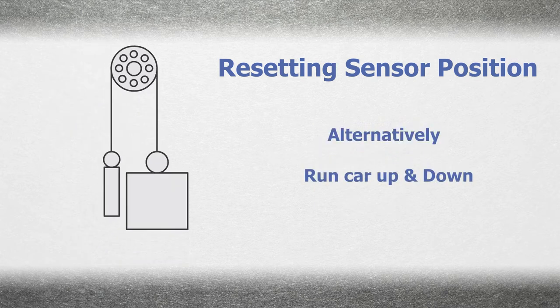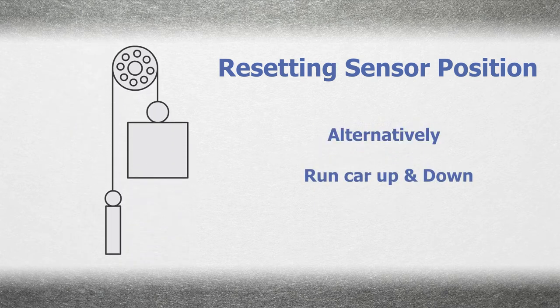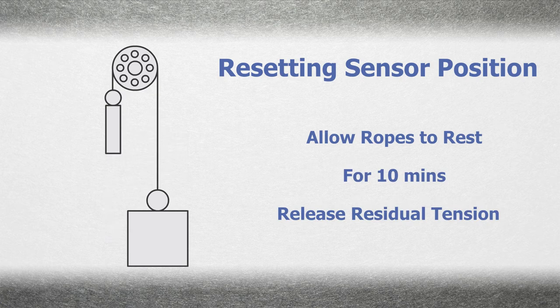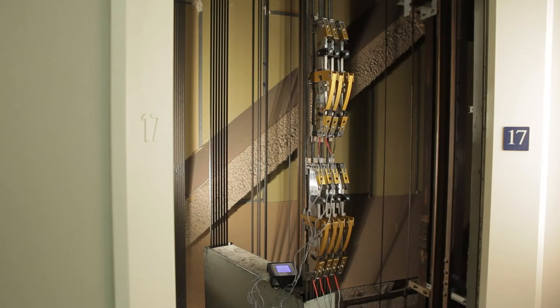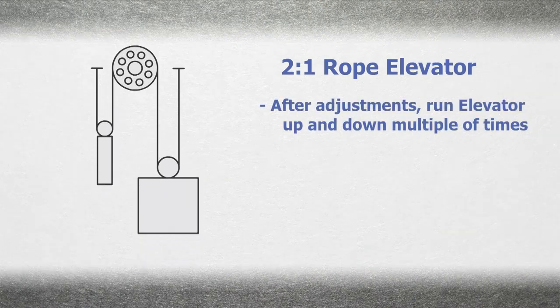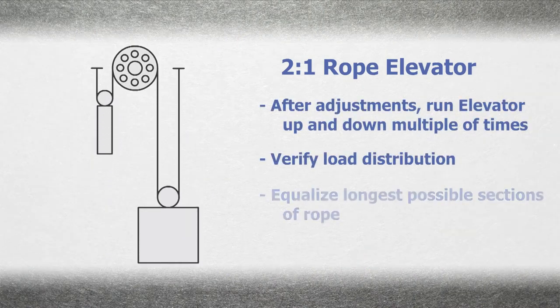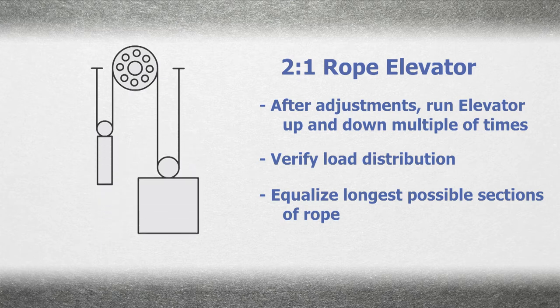Alternatively, you may run the car a bit and allow the ropes to rest for ten minutes to allow the residual tension to dissipate. For a 2-to-1 roped elevator, after adjustments, run the car up and down to verify load distribution. The goal is to equalize the longest possible sections of rope.